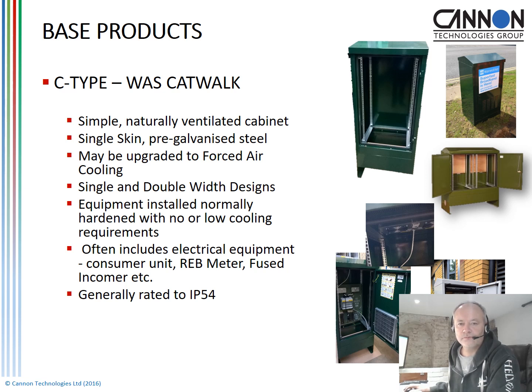Single skin construction equipment is a little bit more rugged to the environment it's been installed in, and we can install forced air cooling fan units which can fit into the roof here, which can be monitored and can either run at a set temperature, set speed, or can speed up or slow down depending on the temperature within the enclosure. We often also install things like the consumer unit, which is then connected to the mains power by the civil or the electrical integrator.